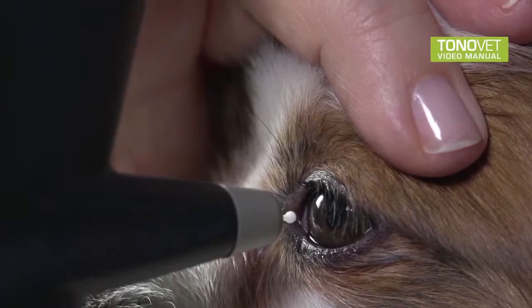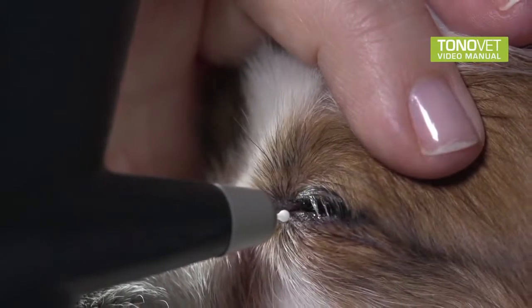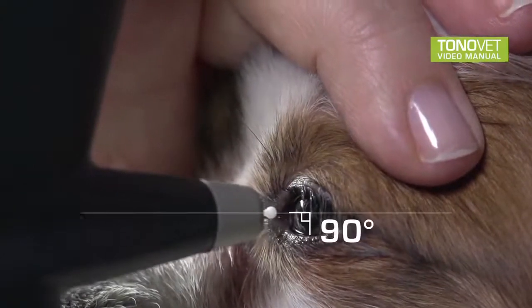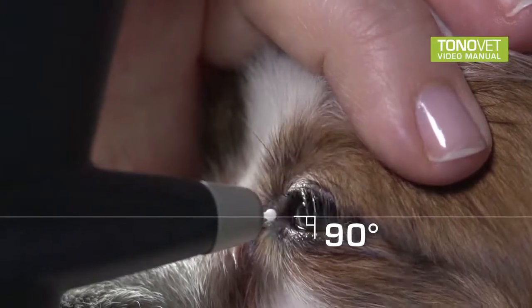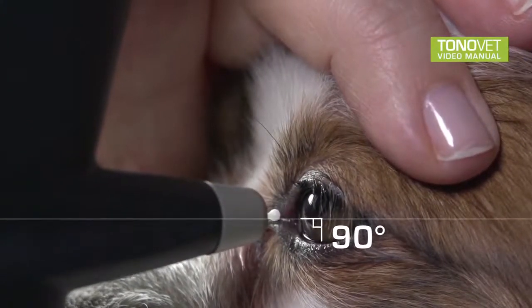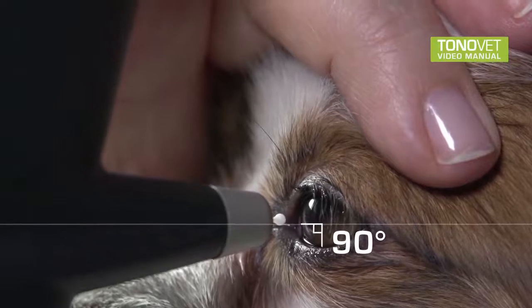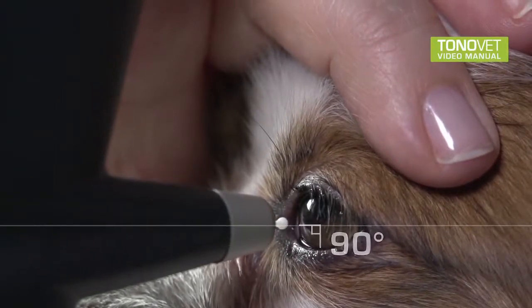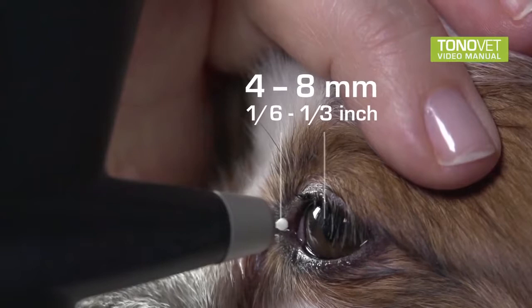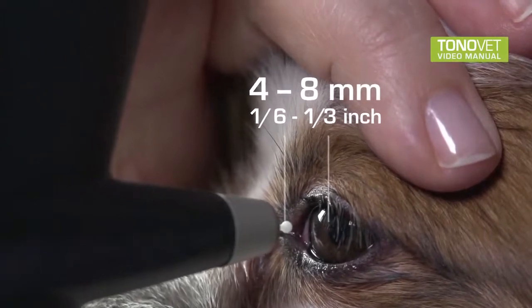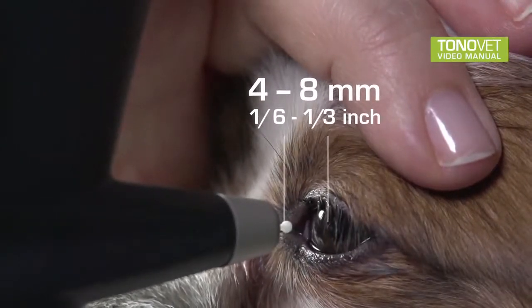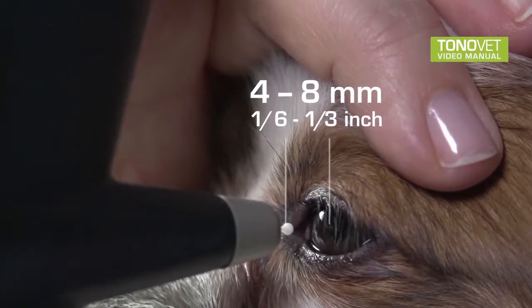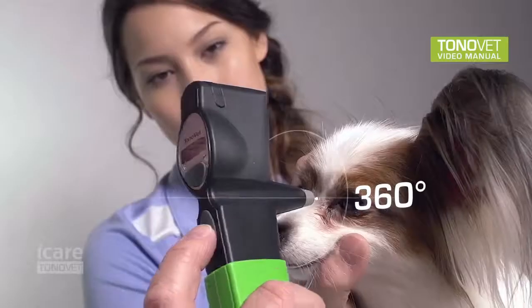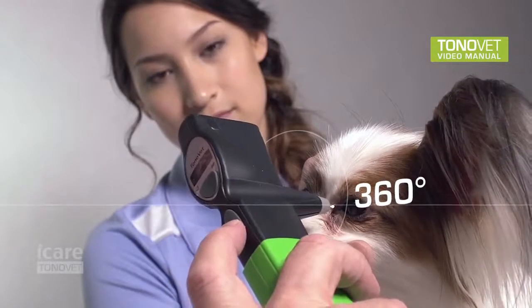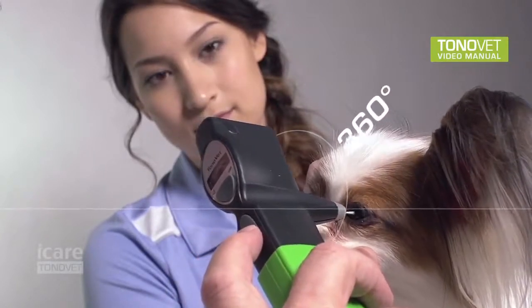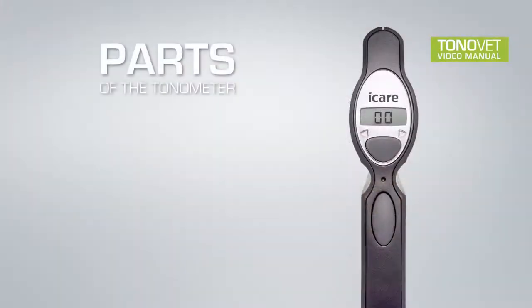When measuring the intraocular pressure with the TONOVET, the tonometer's probe must be aligned horizontally, perpendicular to the central cornea in a 90-degree position. Distance from the tip of the probe to the cornea is 4 to 8 millimeters, or 1/6 to 1/3 inch, respectively. While the probe must be aligned horizontally, the grip can be rotated into a preference position of the user.